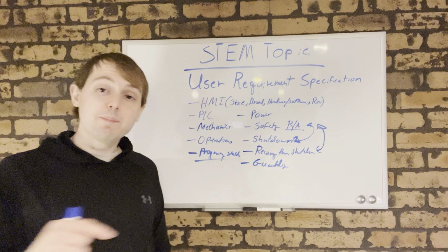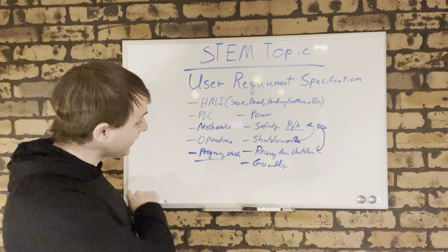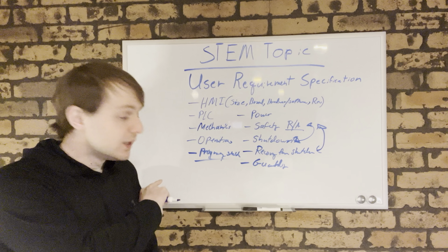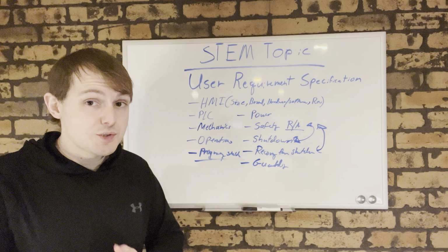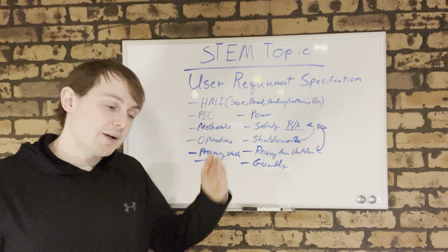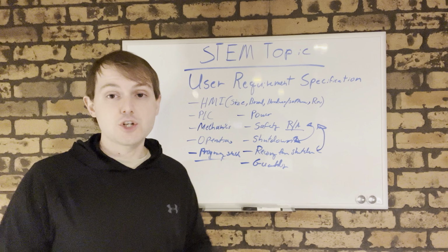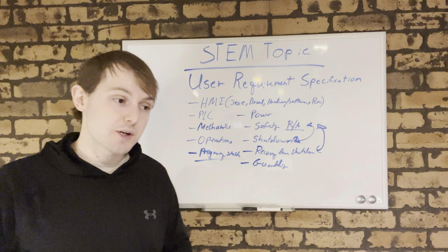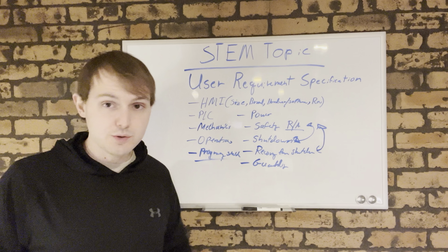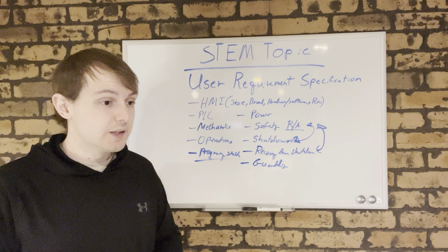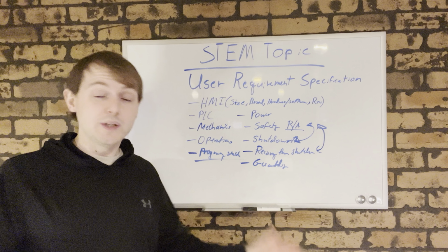Okay? You might put like a programming standard kind of thing, and I know that's not real well to be read, but the programming standard might say something along the lines of, you will not use a sequencer bit, but you will use something like a move equals or a math function that will operate as the sequencer. Or you might say, no, you're not doing that. That's convoluted and messed up. You will use only a sequencer type of function. There will be no bit shifts. There may be only bit shifts.